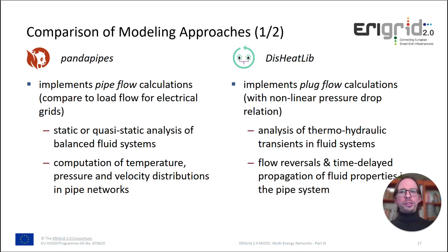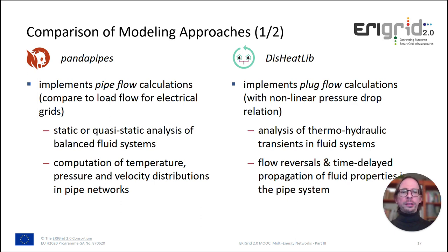Let's look at how the two approaches differ. On the one hand, PandaPipes implements a so-called pipe flow calculation — a static or quasi-static analysis of the balanced fluid system — computing temperature, pressure, and velocity distributions in the pipe networks. DisHeatLib, on the other hand, implements a plug flow calculation, which allows the analysis of thermohydraulic transients in the fluid systems, including phenomena like flow reversals and time-delayed propagation of fluid properties in the pipe system.